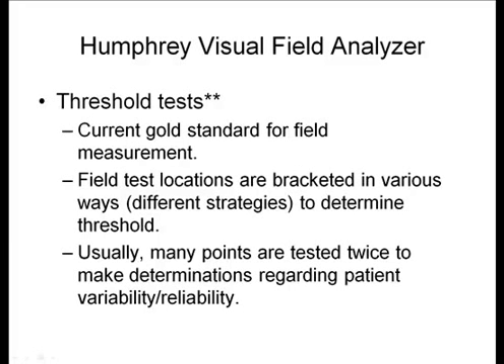Threshold tests are technically the gold standard for visual field measurements. The field locations are bracketed in various ways using different strategies — either SITA standard, SITA fast, full threshold, FASTPAC, etc. — to determine thresholds. They are typically bracketed multiple times to test patient variability and reliability.